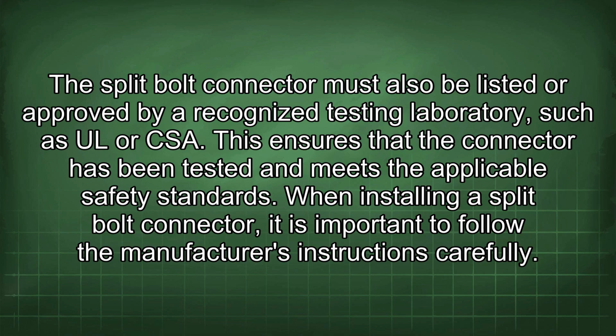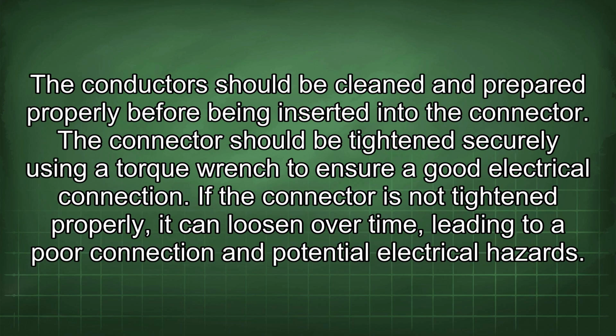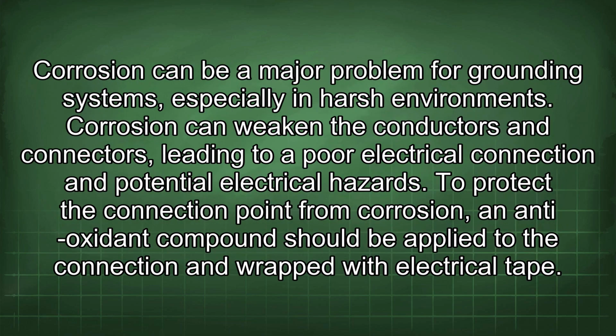When installing a split bolt connector, it is important to follow the manufacturer's instructions carefully. The conductors should be cleaned and prepared properly before being inserted into the connector. The connector should be tightened securely using a torque wrench to ensure a good electrical connection. If the connector is not tightened properly, it can loosen over time, leading to a poor connection and potential electrical hazards. Corrosion can be a major problem for grounding systems, especially in harsh environments. Corrosion can weaken the conductors and connectors, leading to a poor electrical connection and potential electrical hazards.